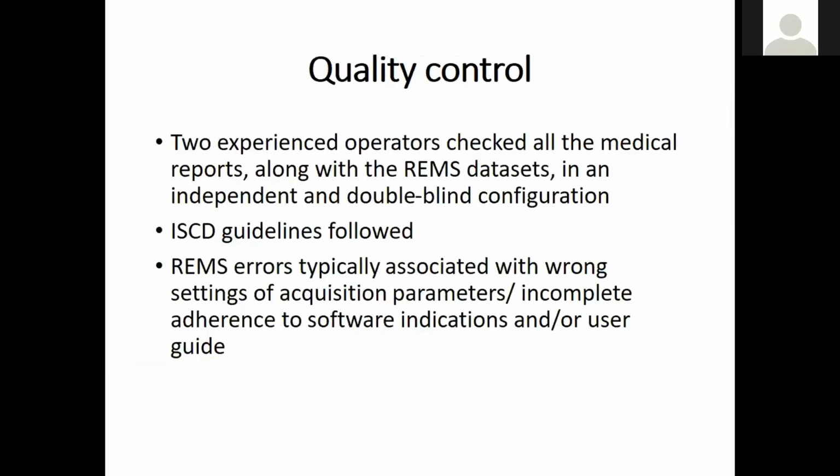So, in terms of quality control, obviously this is an important aspect. Two experienced operators checked all the medical reports and the R.E.M.S data sets, and they did that independently and in a double-blind manner, and ISCD guidelines were followed. So where there did seem to be issues, they were typically associated with the things that I put on this slide: wrong settings of acquisition parameters, or not completely following the software indications or the user guide.